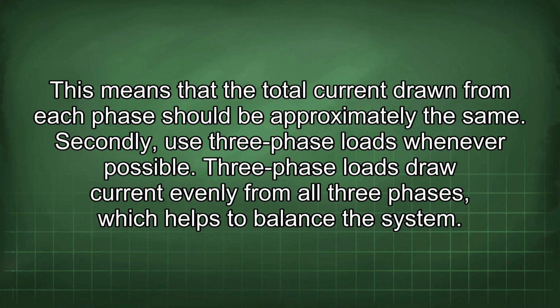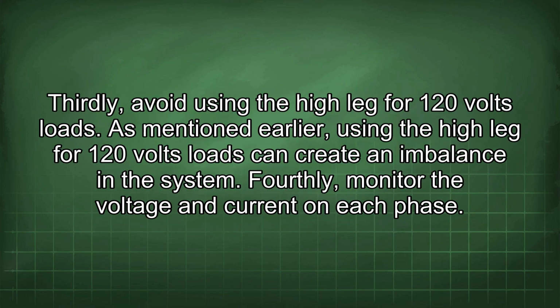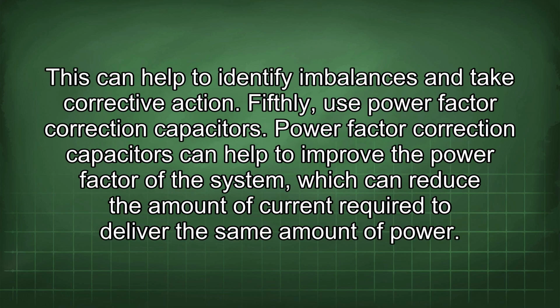Secondly, use three-phase loads whenever possible. Three-phase loads draw current evenly from all three phases, which helps to balance the system. Thirdly, avoid using the high leg for 120 volts loads. As mentioned earlier, using the high leg for 120 volts loads can create an imbalance in the system. Fourthly, monitor the voltage and current on each phase. This can help to identify imbalances and take corrective action.